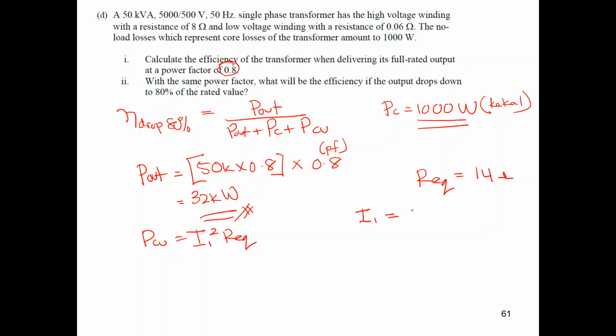The I1 is based on the new S. This means S over V1, but the S has dropped to 80% of the rated value, so that means 50k times 0.8, divided by 5000.